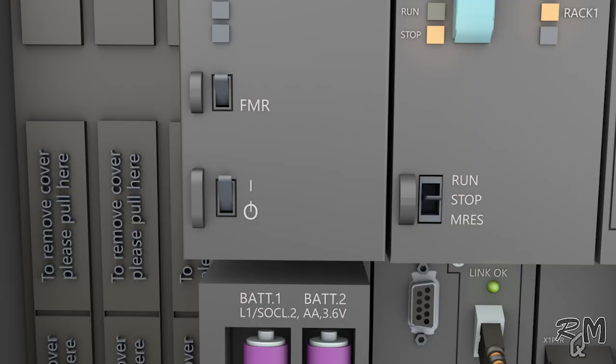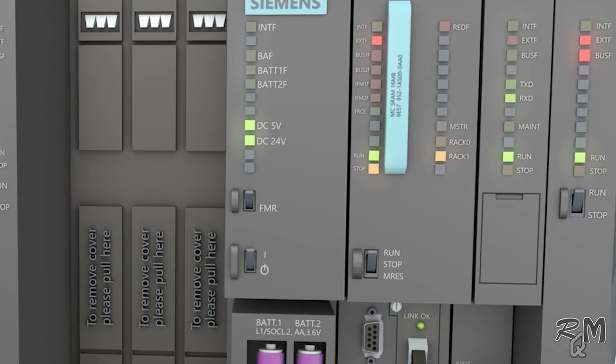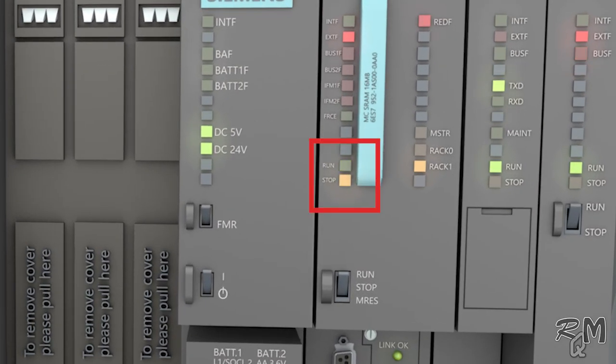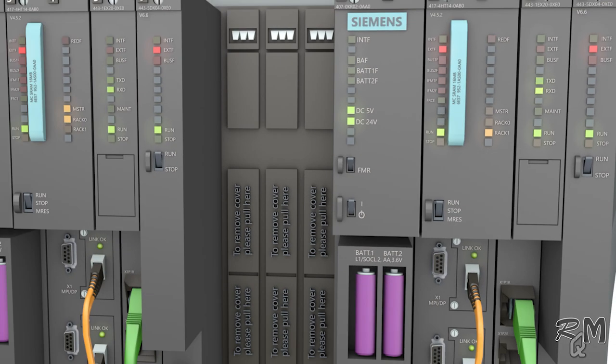Then switch CPU to run mode. You can see run LED is flashing now which shows that program is going to copy from rack 0 CPU to rack 1 CPU. It will take some time depending on the size of program. After complete transfer of program, green LED will become on and stop LED will switch off, which shows that redundant CPU is synchronized and ready for work.